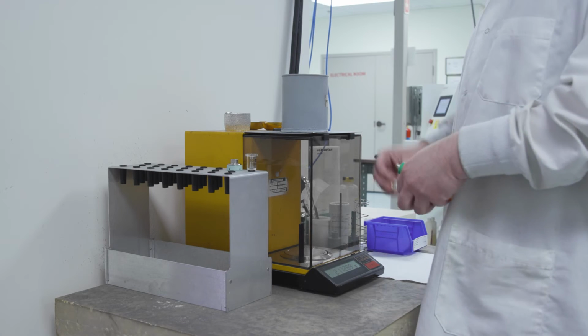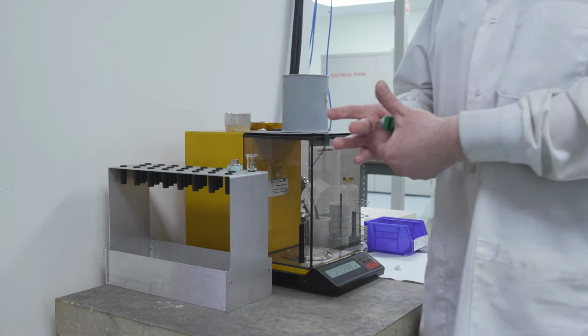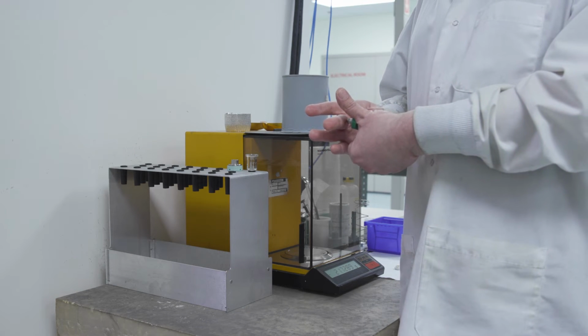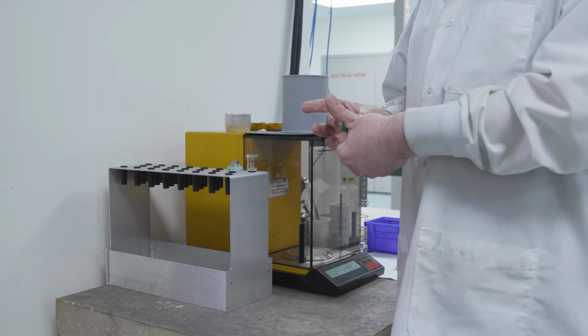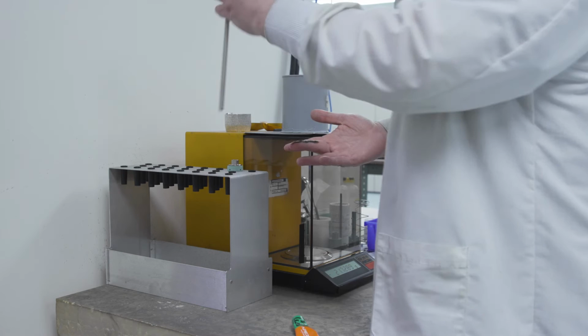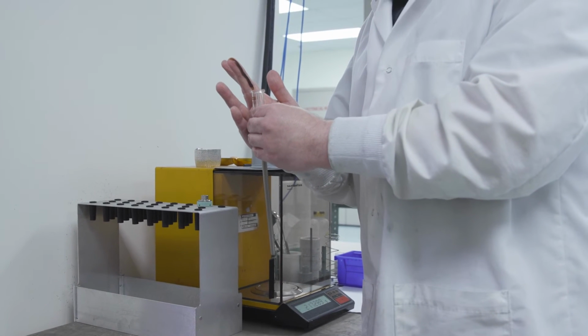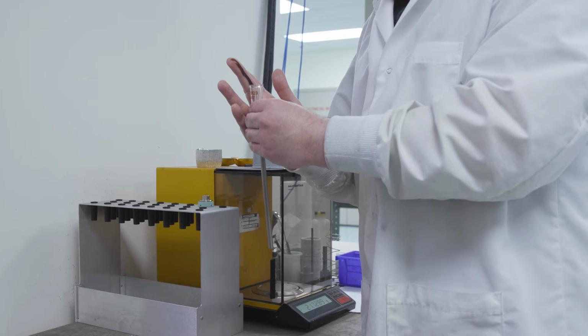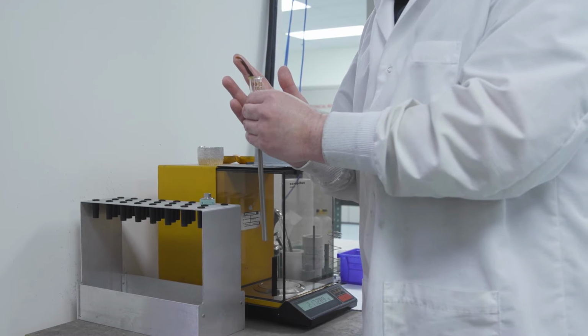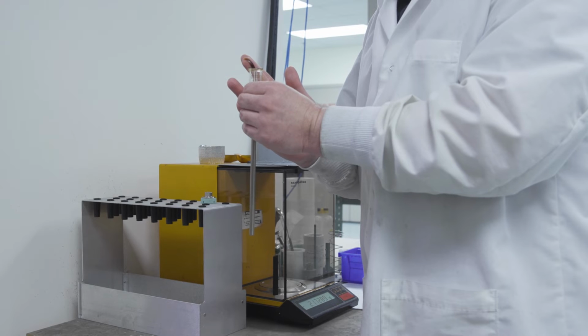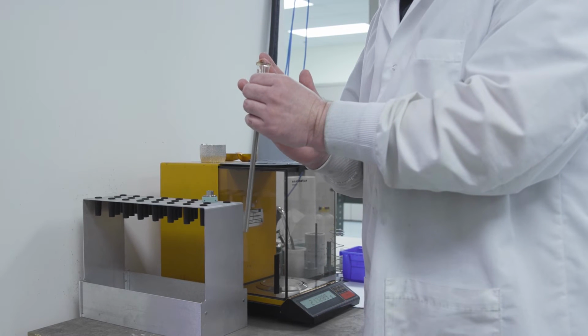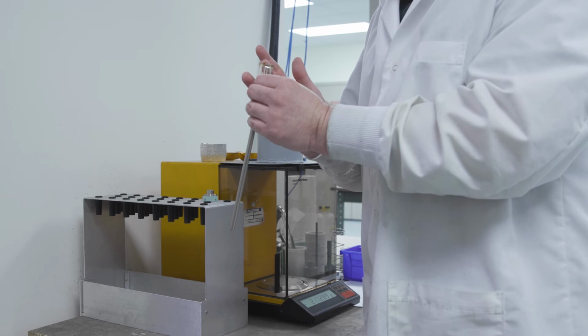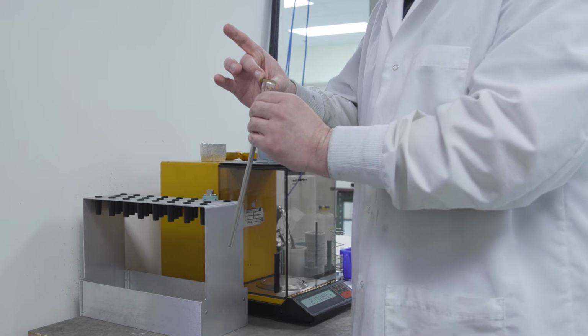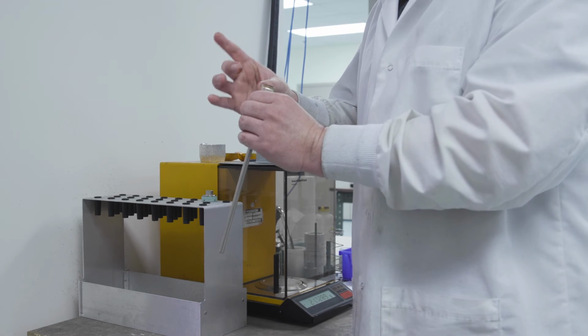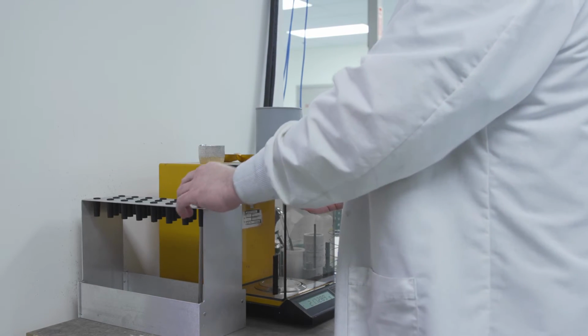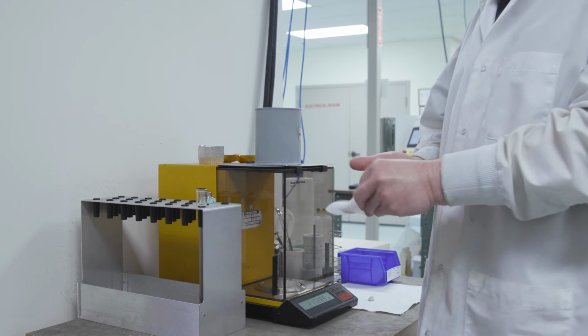As with preparing a sample for analysis, we need to seal the penetrometer, only this time doing so without adding sample. Chris starts with a line of Apiezon H grease on his finger, then applies it to the penetrometer by rotating and lifting the top of the penetrometer along the line of grease on his finger, effectively removing most of the grease and transferring it to the sealing surface of the penetrometer. He removes any excess grease from the outer edge of the penetrometer. And from his finger.